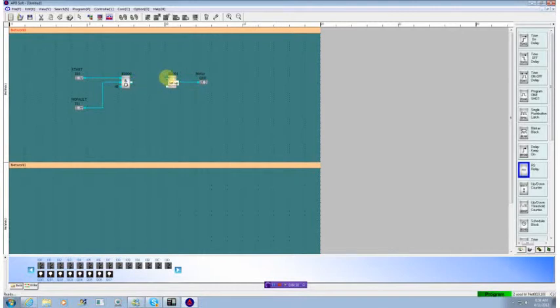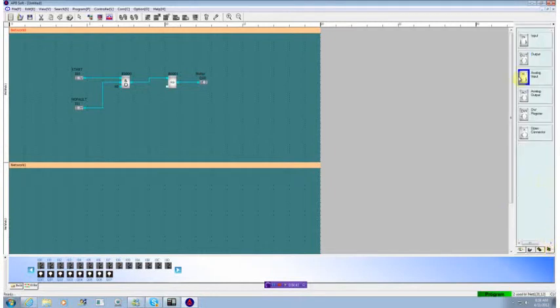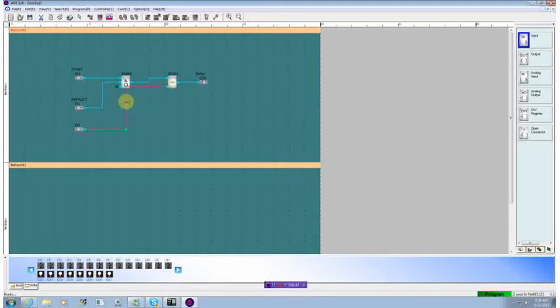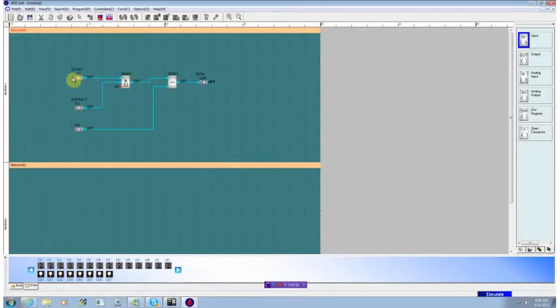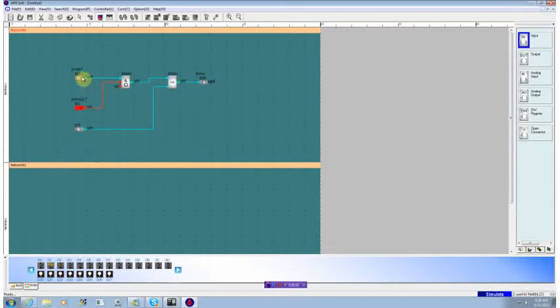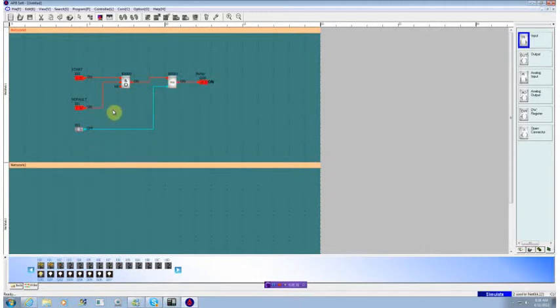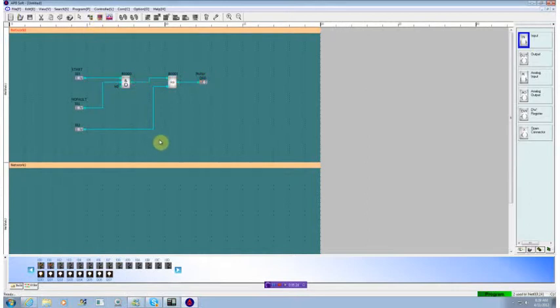And connect the output through. Over here we see that this is the set. And now we need to add some way to turn this off. So we'll go back to our simple IOs and we'll move an IO point over here and set that to the reset. So now when we run our simulator, again, we turn it on and release the start switch, hit the off switch and it turns off. We'll also notice that if we turn it on and don't release the start switch, when we hit the reset or the off, the reset takes precedence over the set and so it will still turn the motor off. So we now have a motor running with a conventional start-stop capability.